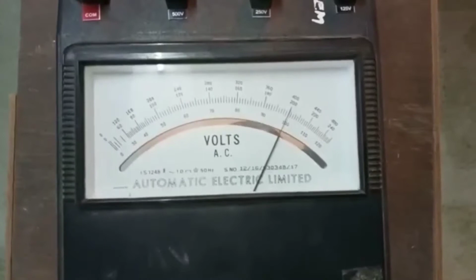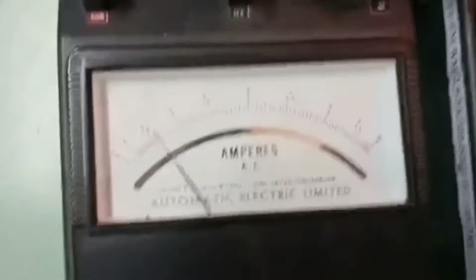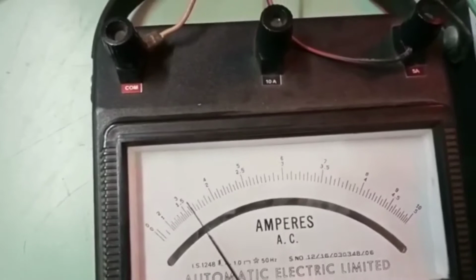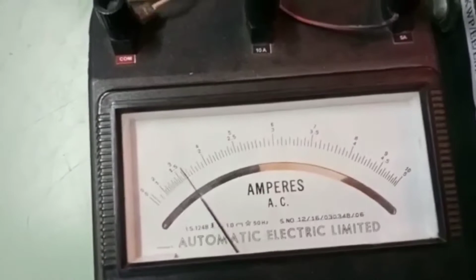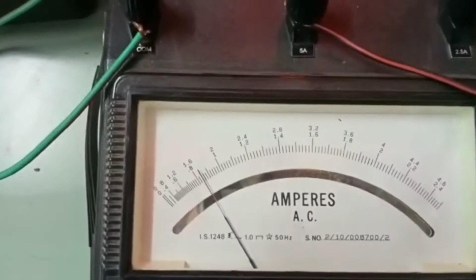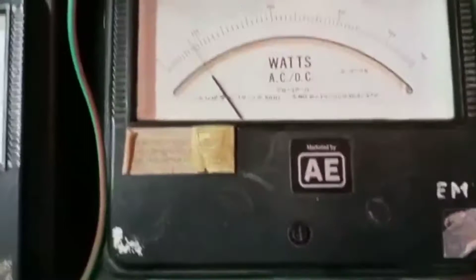For the second switching position of resistive load, the line voltage is 400 volt, phase voltage is 228 volt, line current is 1.65 ampere, and phase current is also 1.65 ampere. Wattmeter W1 shows 120 watt.